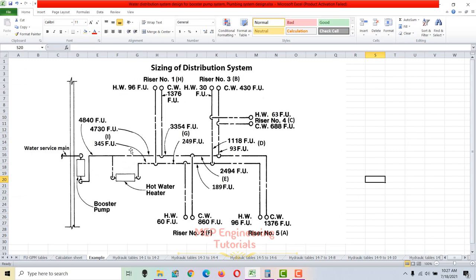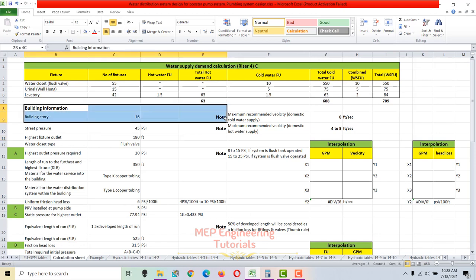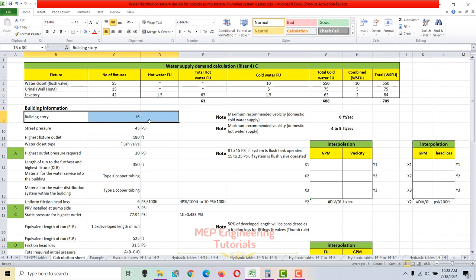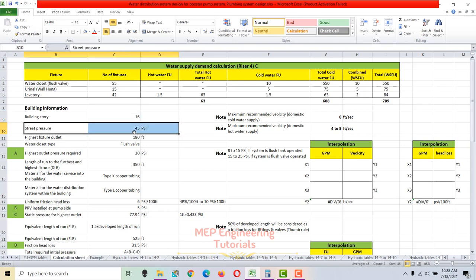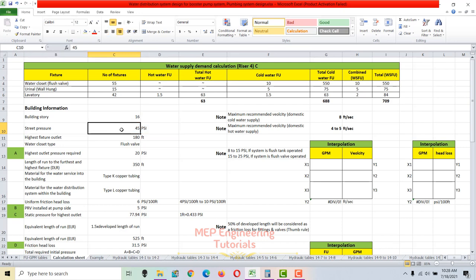This is the example we are going to cover in this session. We have a water service main line from the street main. The building is 16 stories, so I write 16 stories here. The street pressure — you get this from your local authority. In our case, the local authority reported the street pressure as 45 psi.